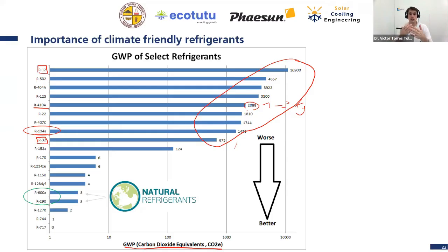And you know, these cooling systems normally lose a little bit of gas, so they have to be refilled and so on. So we have to be aware of that. And we cannot really say a solar cooling system is sustainable if it uses one of those refrigerants, because we are saving, we are being efficient by using solar, but not sustainable using the refrigerant. So that's why it's very important to use natural refrigerants.